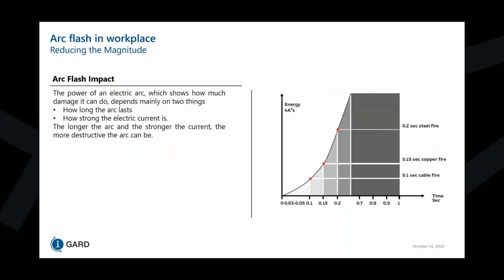So this is where our arc flash relay comes in. As you know, the arc flash impact, the power of an electric arc, which shows how much damage it can do, depends mainly on 2 things: how long the arc lasts for, and how strong the current is. So the longer the arc and the stronger the current, the more destructive the arc can be. So you can see that even 0.1 seconds or 0.15 seconds can be problematic. 0.2 seconds, you can have steel fire.